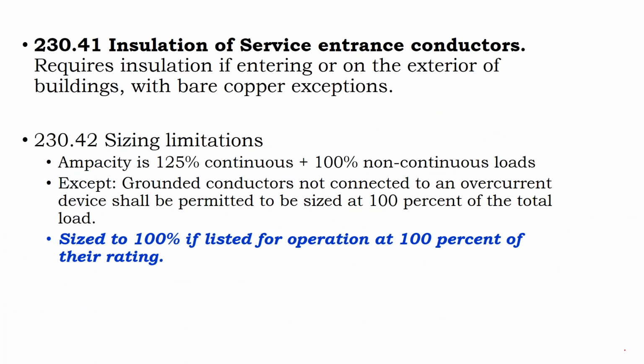Service entrance conductors are sized for 125% of the continuous and 100% of the non-continuous loads. That's just a general sizing principle when you're looking at the ampacity of your continuous loads. You add 25%. Your non-continuous loads may be sized for less than that. In solar, they'll say on the DC side, when you're not controlling the power with something like a DC optimizer, you size for 125% of the amperage output of that panel, but even before you get to that point, you have to throw on an additional 25%. And a lot of solar guys say that's weird, that doesn't show up in any other part of code.